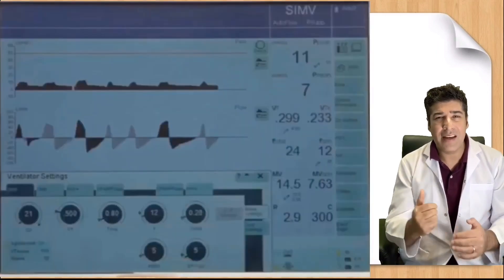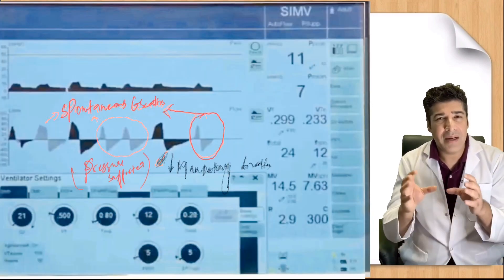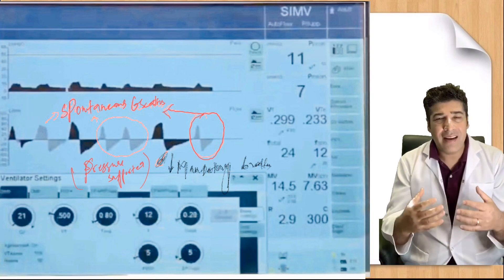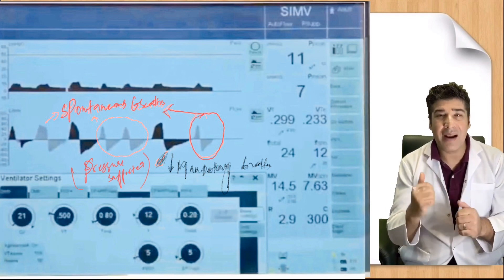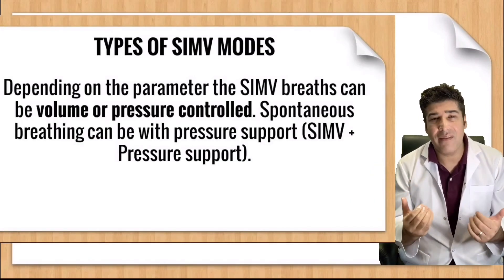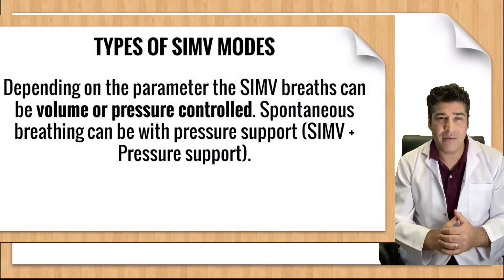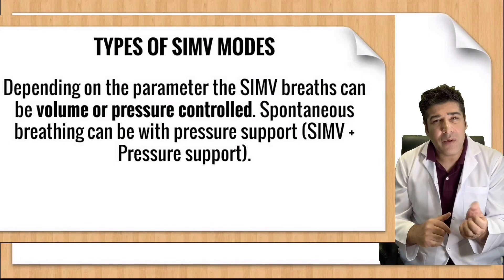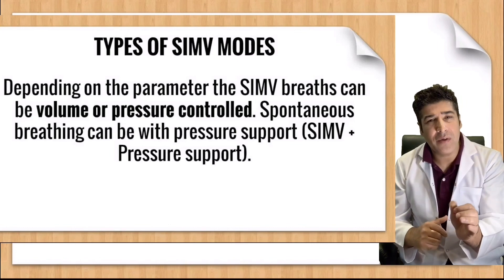In the second picture on the slide, the patient is allowed to take spontaneous breaths — the patient is receiving mandatory breaths as well as being allowed to take spontaneous breaths, and these spontaneous breaths are pressure supported. There are two modes of SIMV ventilation: it could be volume control or pressure control SIMV. If they have pressure supported spontaneous breaths, they are known as SIMV volume control plus pressure support, or SIMV pressure control plus pressure support.